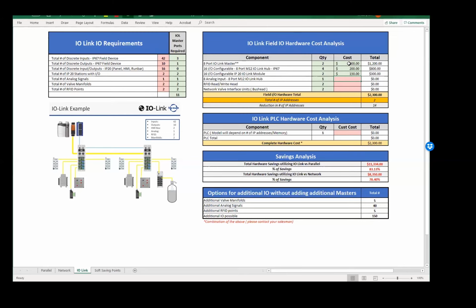And also analog. We're going to put our IP67 block out there. Even though we're only using 1 of those ports, we have 7 available on that IP67 block. We're at $350. That's amazing. It was $650 for a 2-port analog card. Yeah. So you imagine, as soon as you start having a couple analog points, using IO-Link can save you quite a bit of money.